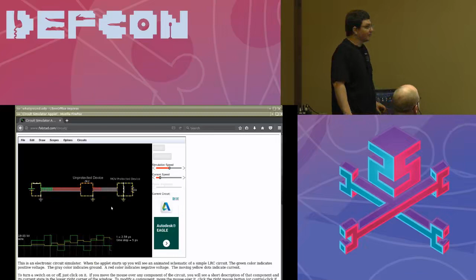If you have a good surge protector over here and you have no surge protector over here, you can actually send a reflection back to this first device. And I think it was Square D that has a white paper on this, about reflections from surge protectors actually causing more damage. Obviously, they want to sell you surge protectors for every device. But the simulation bears out that it can reflect, and it can cause a secondary surge that could actually be stronger than the first surge.